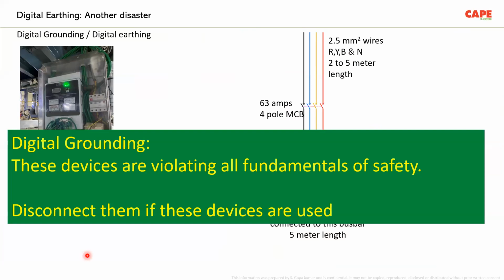An electronic equipment can work even if the potential between neutral and earth is higher than 1 volt or even 12 volt in an electrical apparatus. Even if the neutral to earth voltage is 30, 40, 50 volt, nothing happens to your equipment. Remember, this neutral to earth voltage of 0 or 1 is applicable only for an earthed network. If you go for an unearthed network, such as an IT system, then the neutral to earth voltage can go up to 230 volt. All your equipment are designed to work up to that particular voltage. Even if the potential between the neutral and earth is 230 volt, your equipment is supposed to work.